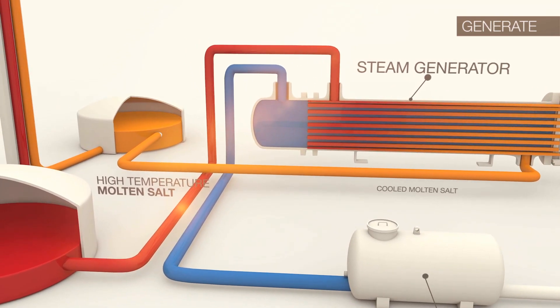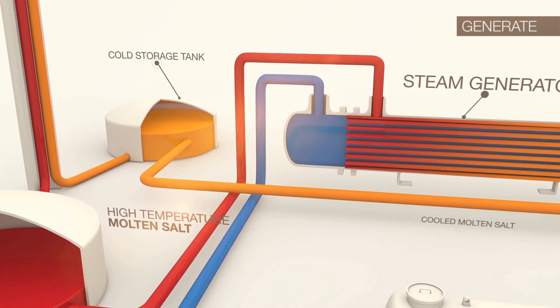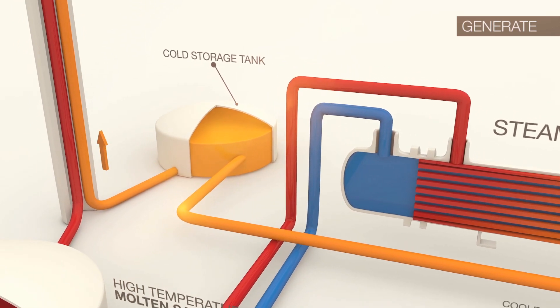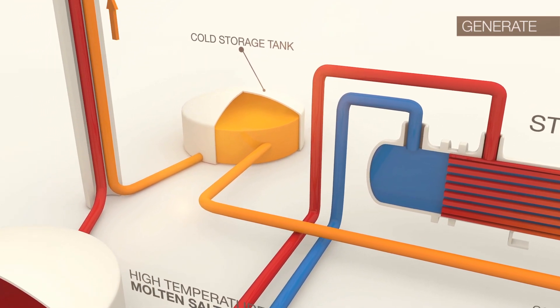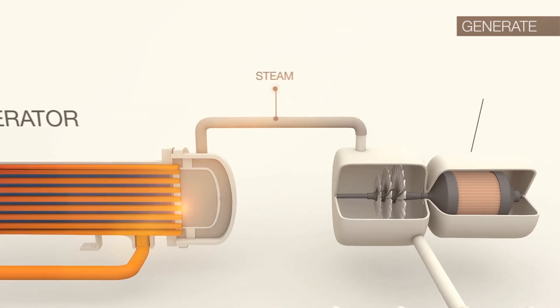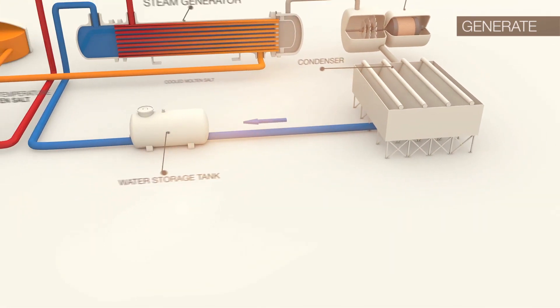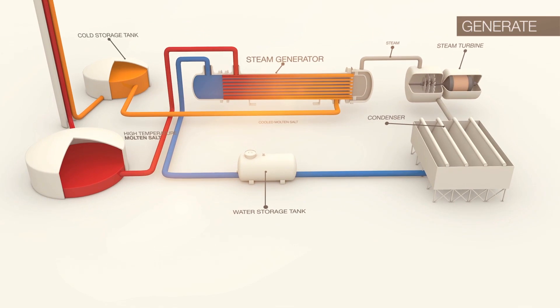Once the hot salt is used to create steam, the cool molten salt is then piped back into the cold salt storage tank where it will then flow back up the receiver to be reheated as the process continues. After the steam is used to drive the steam turbine, it is condensed back to water and returned to the water holding tank, where it will flow back into the steam generator when needed.